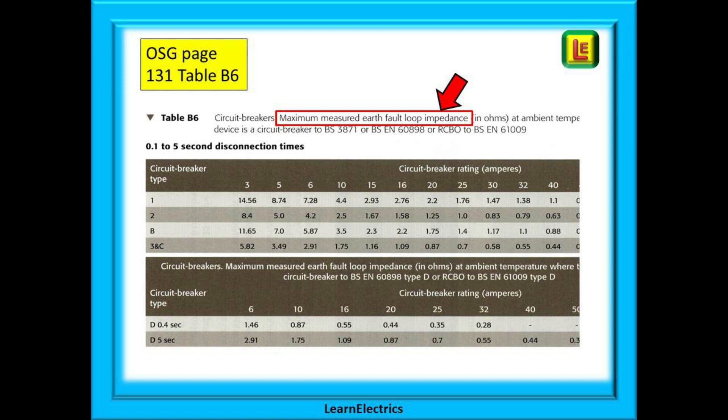If we look in the on-site guide page 131 we will find table B6 for ZS values. The values in this and neighbouring tables will sometimes be called the 80% values or the measured values. They will give us the maximum measured earth fault loop impedance for a particular breaker or fuse. How should an electrician use this information, and why are there different values? You should already be familiar with how to measure ZS and the parts of the circuit that the term ZS applies to. If not, look it up on one of our other LearnElectrics videos.